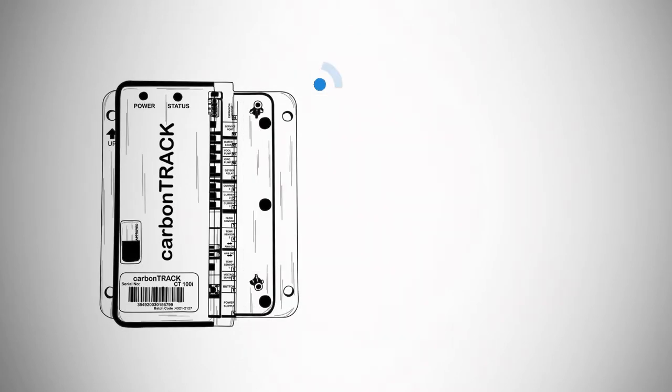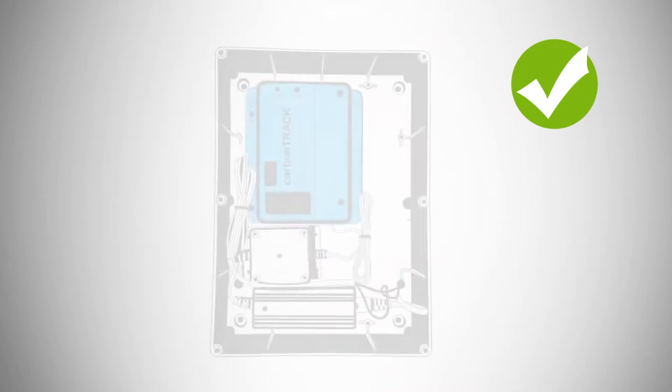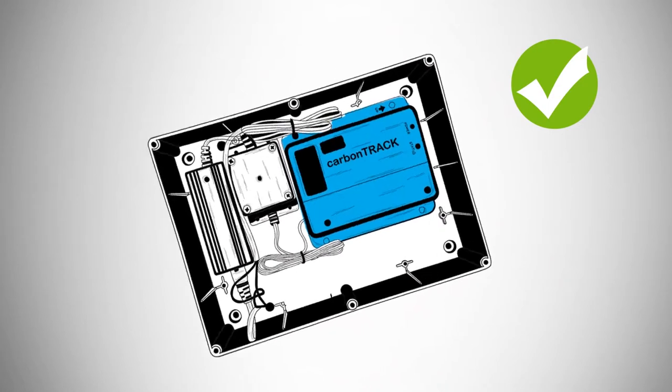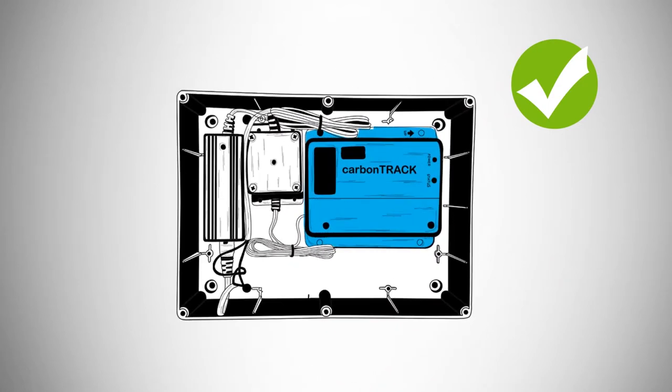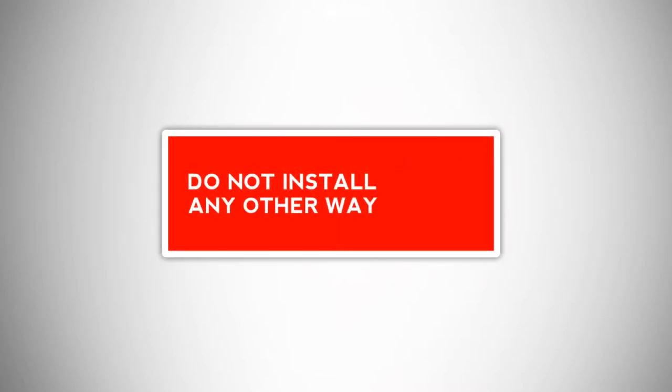Also, check that there is proper signal coverage at installation for the GPRS modem. Mount the CarbonTrack unit with the aerial pointing upwards. The unit must be installed upright or on its side with the CT unit on the top right corner position. Do not install any other way.